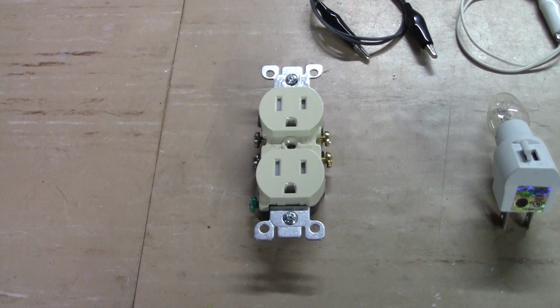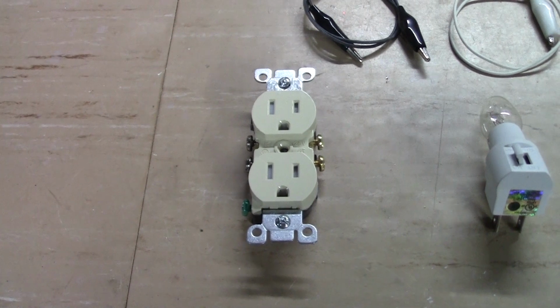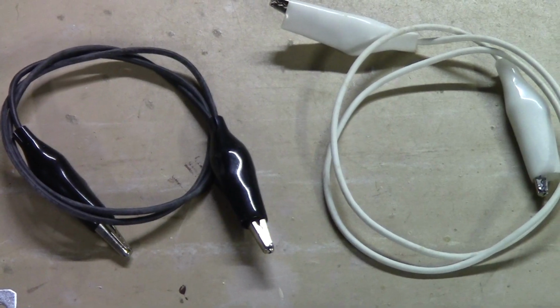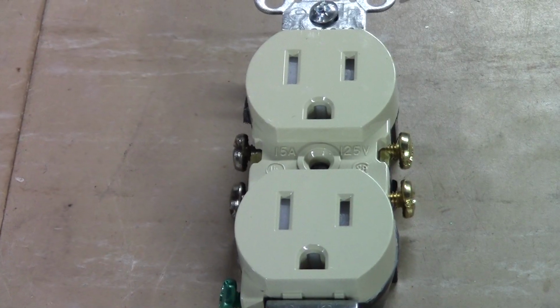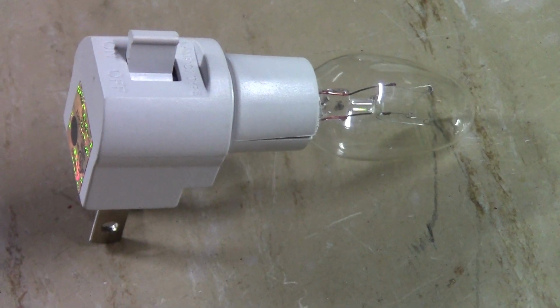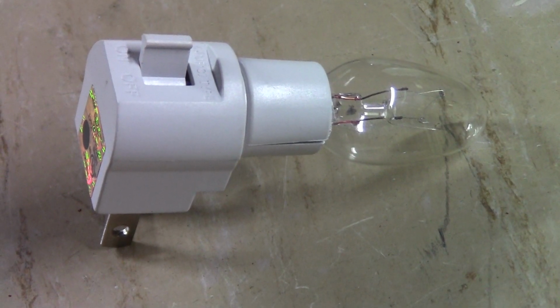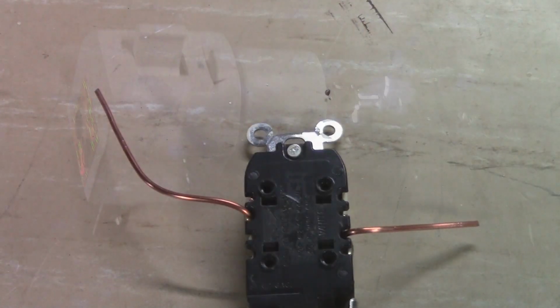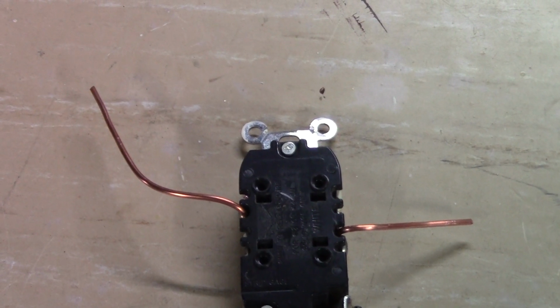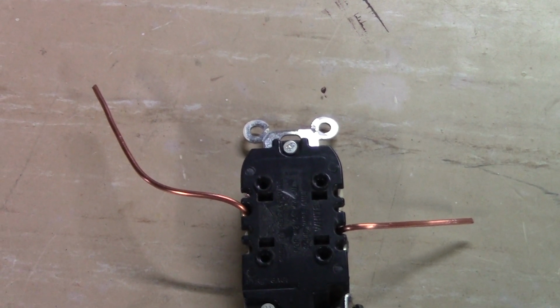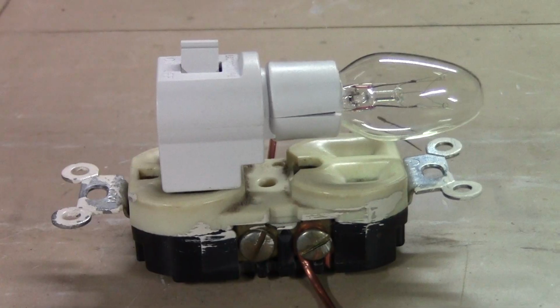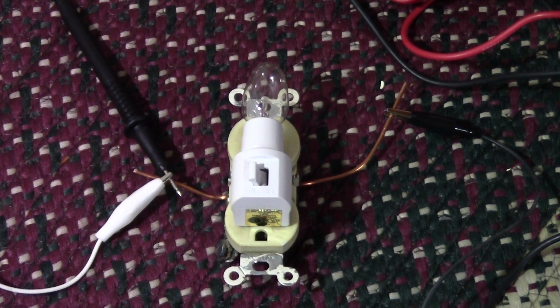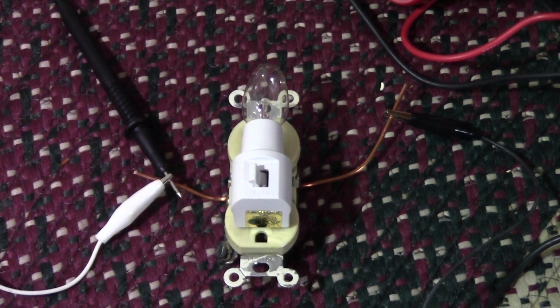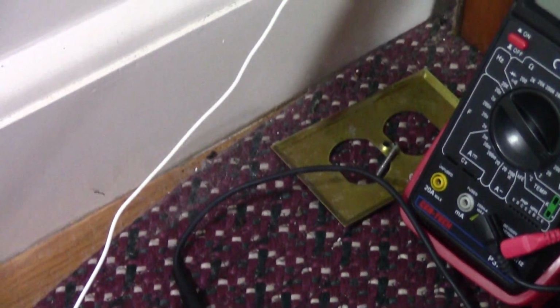First, you will need to collect some common parts. You will need 2 clip leads, a spare outlet, a 4 to 7 watt night light, preferably one that has an on-off switch. Start by connecting a couple of bare wires to the hot and neutral connections of the outlet. Plug the nightlight into the outlet. Connect the black DVM probe with a white clip lead to both the neutral on the outlet as well as the neutral on the circuit you are testing.